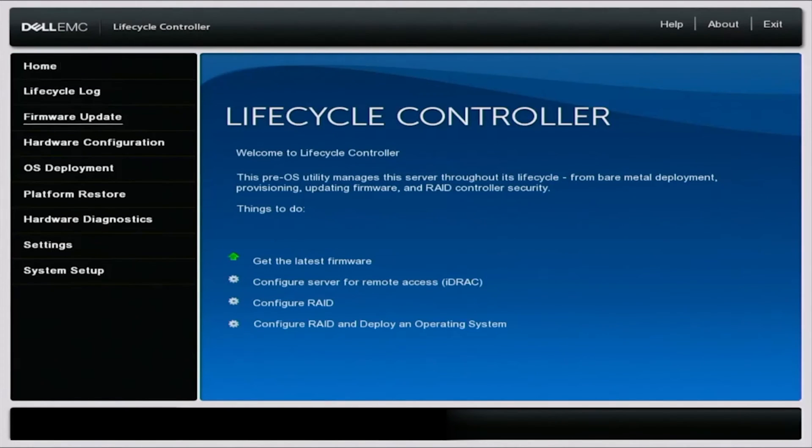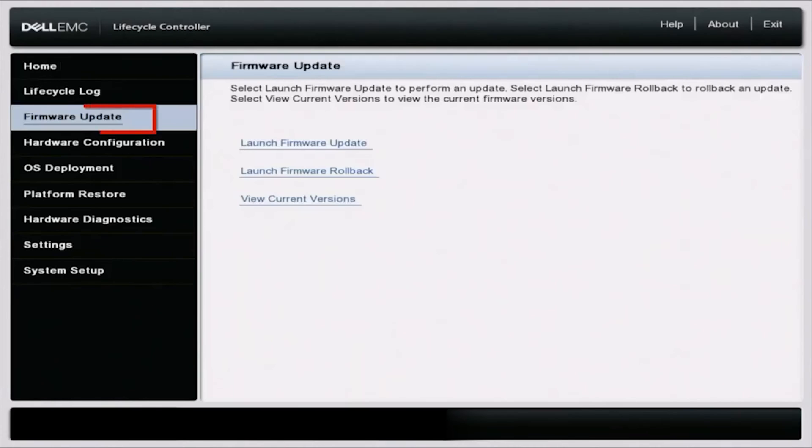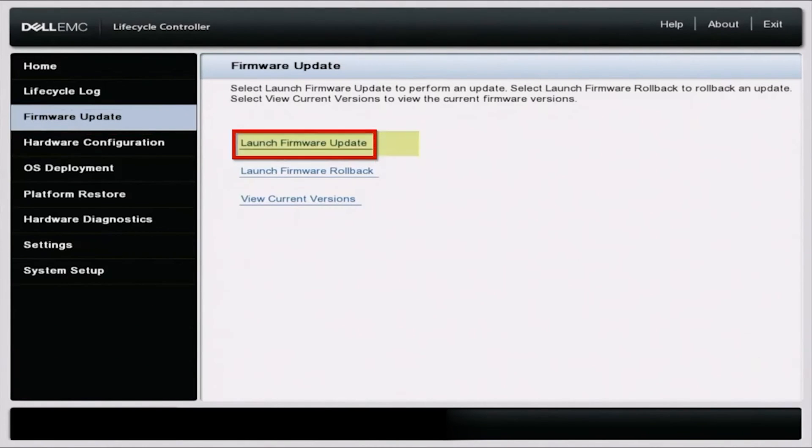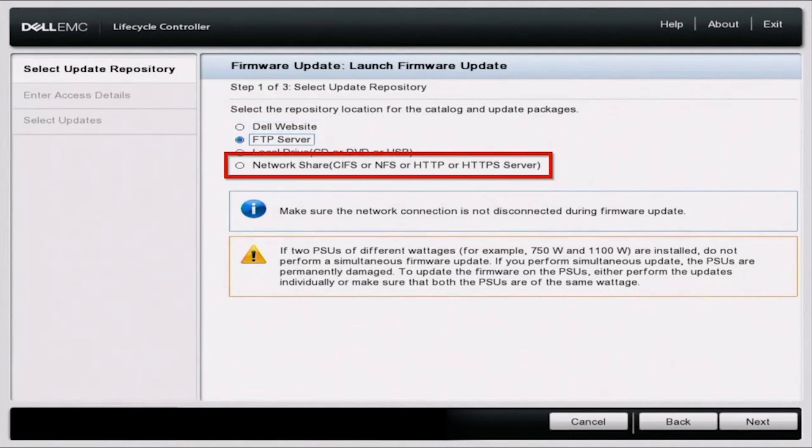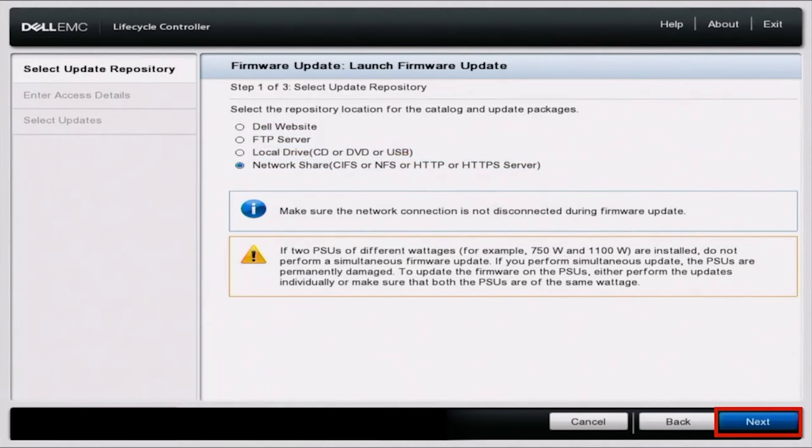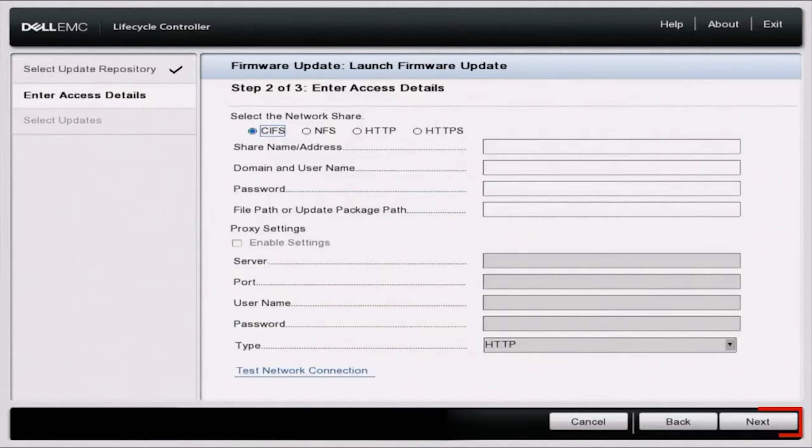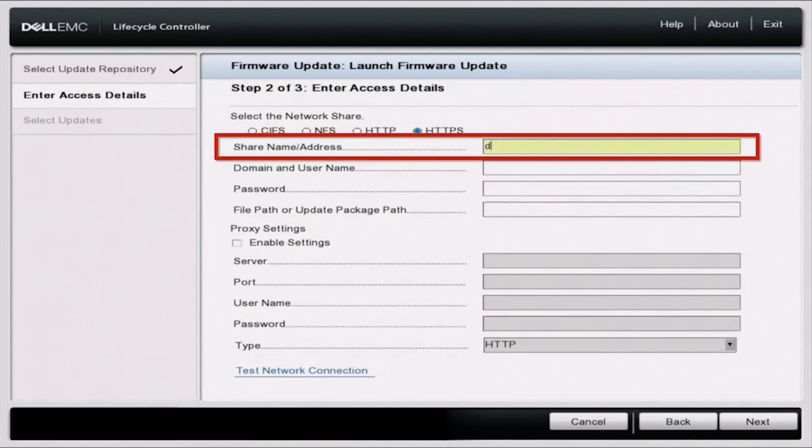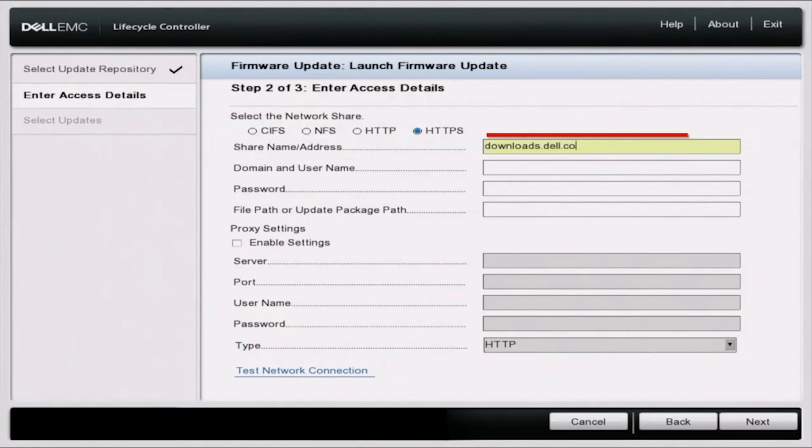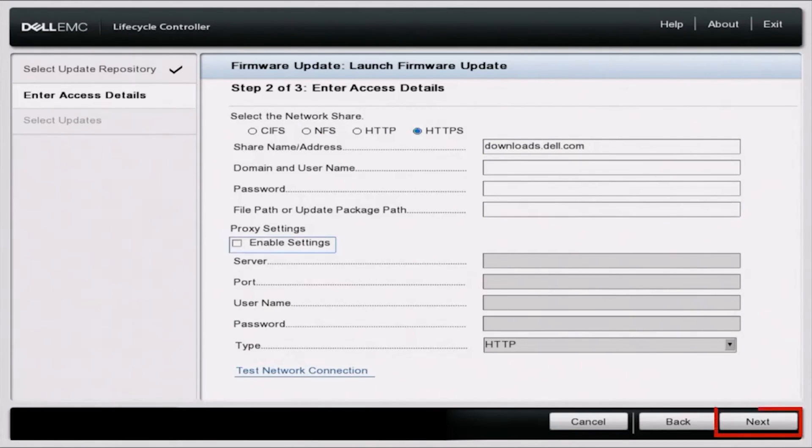So once we've done that, we want to scroll up to firmware update and then click on launch firmware update. And here we want to scroll down and select network share, and then we can click on next. Up here, we want to change this to HTTPS. And then we want to type in the shared name address, which is going to be downloads.dell.com. Once we've typed that in, scroll all the way down and then just click on next.